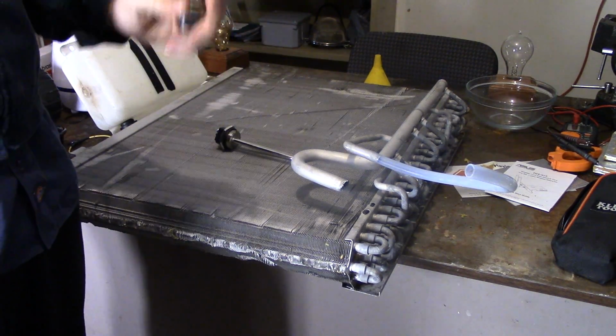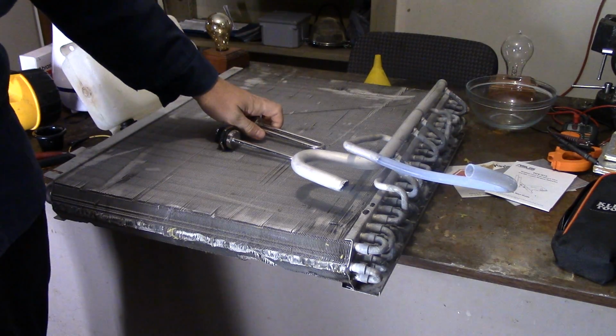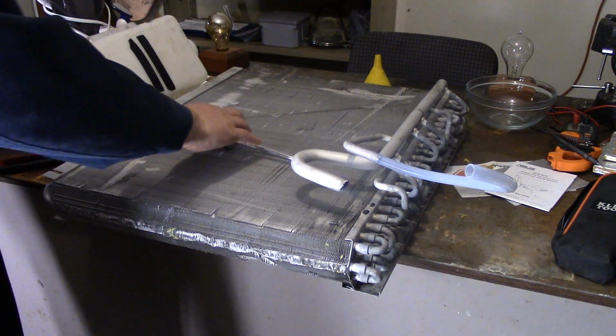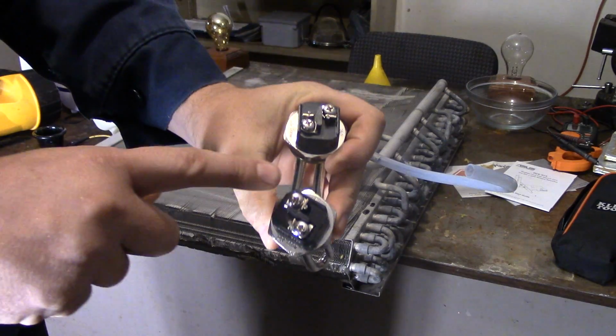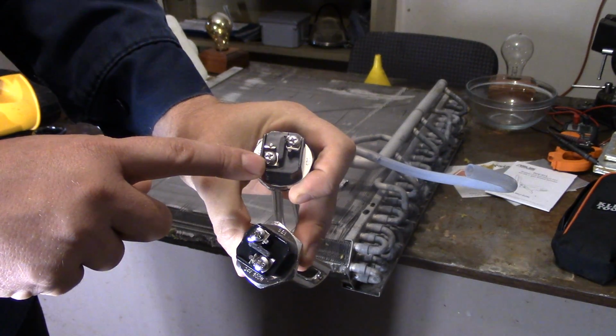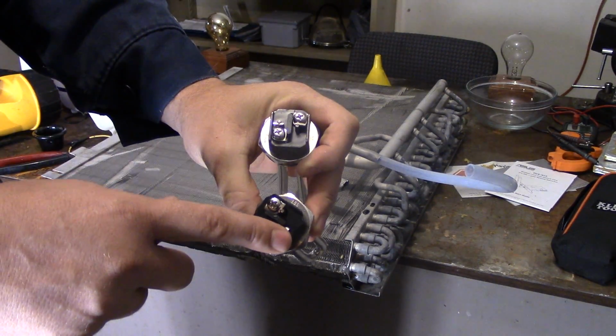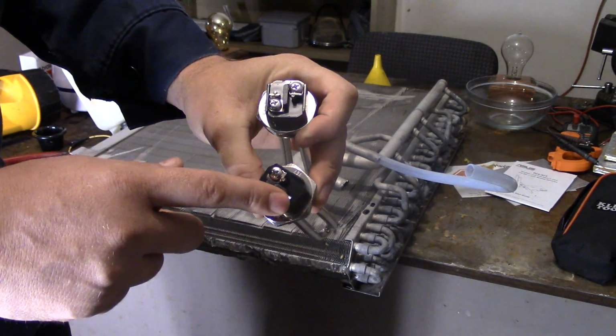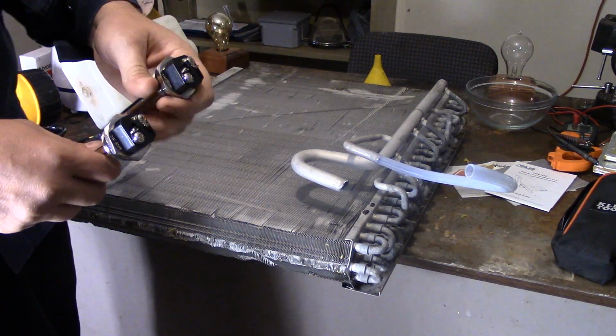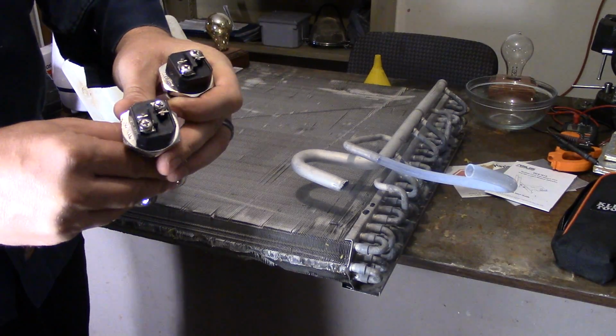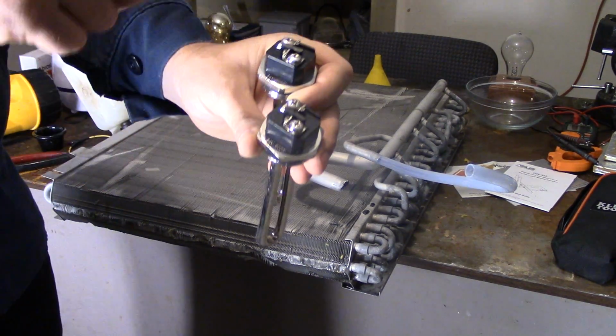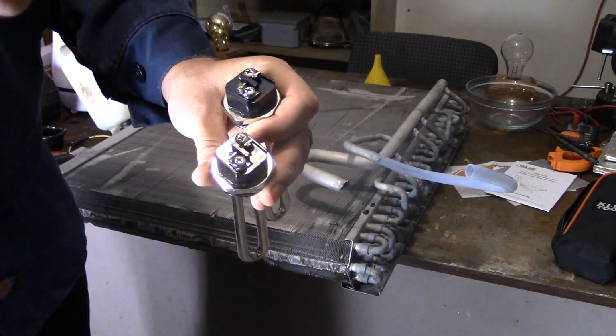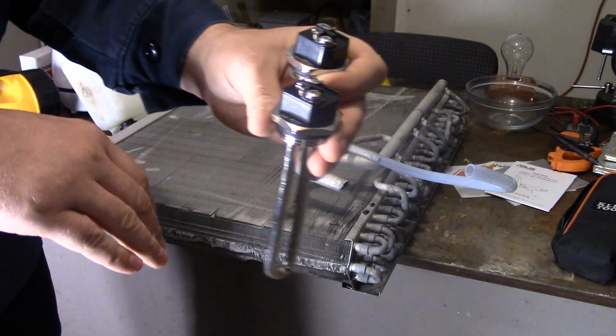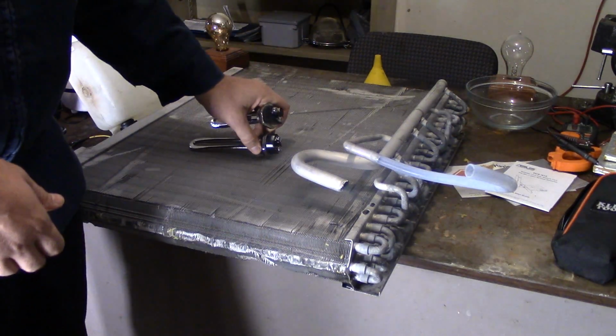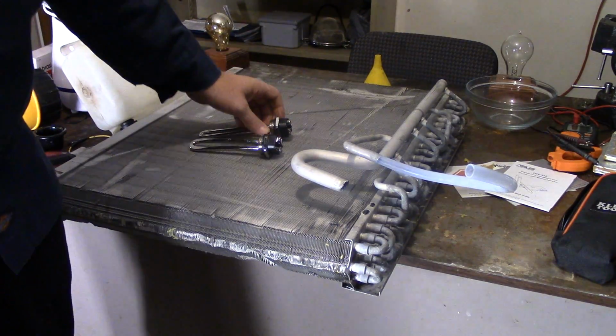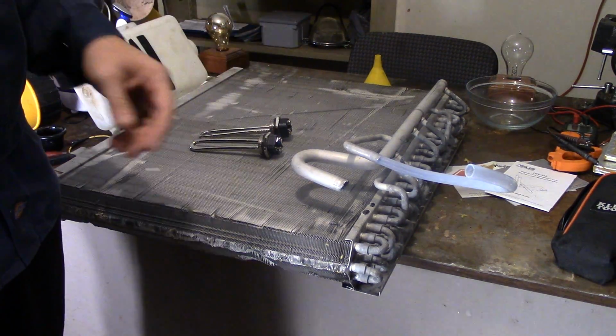Now, since they're DC power at 24 volts, if I run a number 10 gauge wire from here to here, and from there to a positive and negative on a 48 volt battery bank, I'd have 24 volts on this element, 24 volts on this element, 25 amps going to both since they're identical elements - that's 600 watts each.